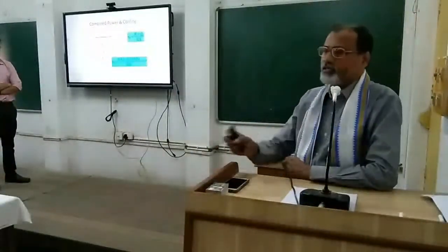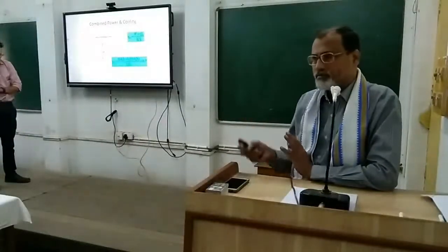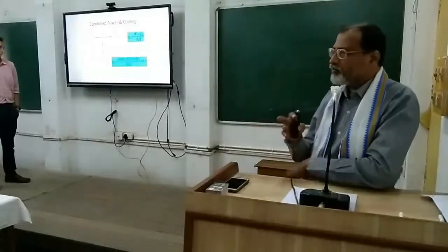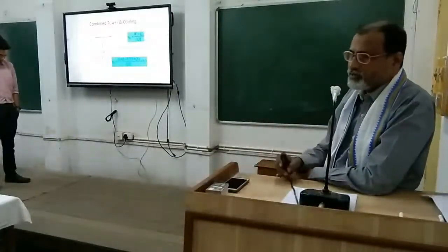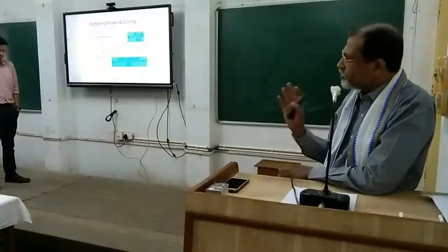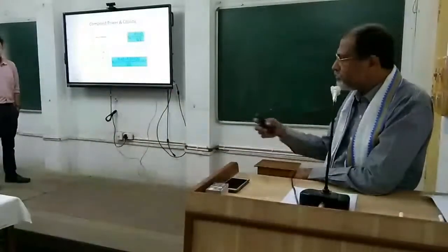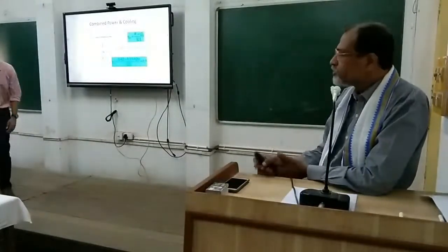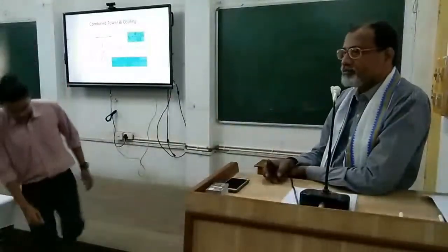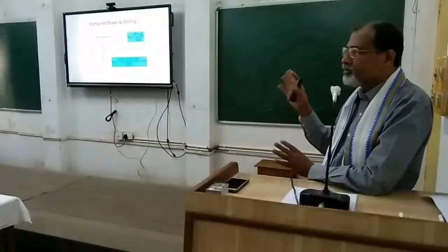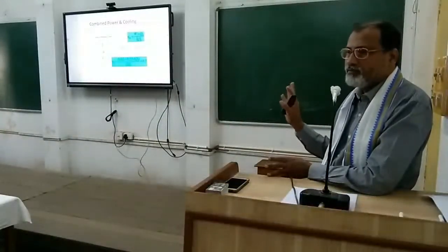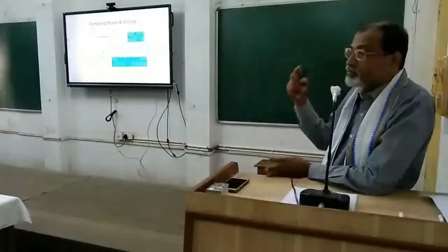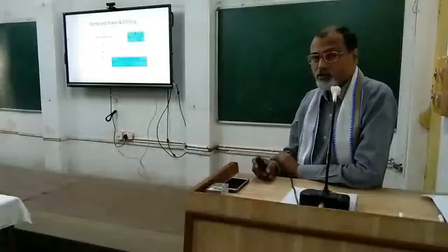The second law says you have to reject heat to produce work. You cannot convert 100%, isn't it? So if you cannot convert 100%, there is always going to be some rejects. So if there is going to be rejects, why not use those rejects to run a VAR system? That again will give me some cooling. So that's what I attempted doing. And then I tried to use the same assessment technique, and I find this system is showing me an efficiency of 70%. Good enough.